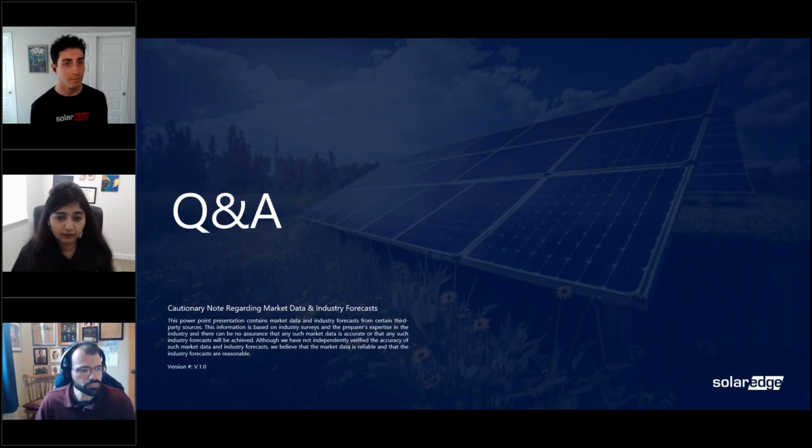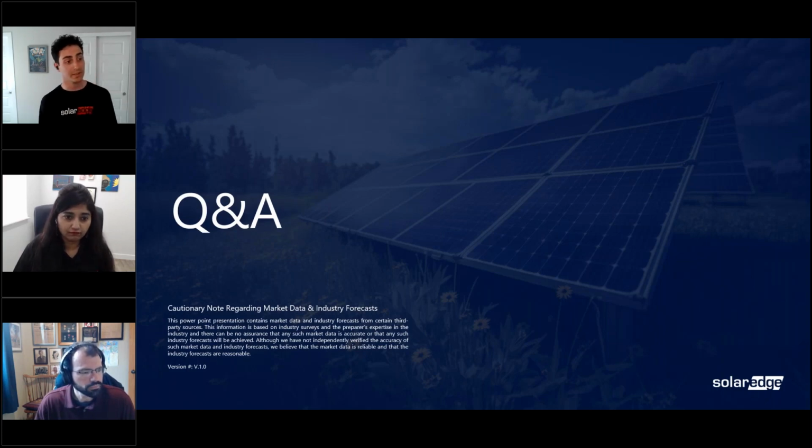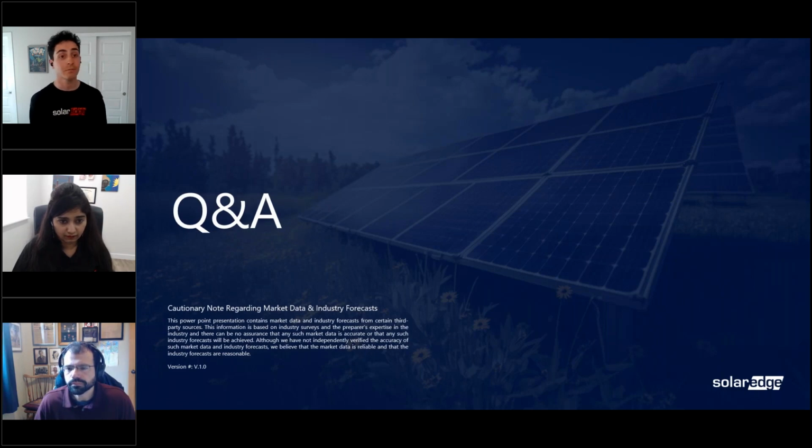Yeah, thanks, Clever. I see a comment from Susan. Susan says Hellermann Titan ties are designed to last 25 years. Yeah, thanks for that comment, Susan. It's a good point. And there are zip ties that are listed with some of these systems that have ratings for longer lifespan. What I would note is that the warranty level on these ties is still usually between 1 and 3 years. So just something to note. And obviously, the concern that we have with zip ties is that you don't know when they break. There's no way to actually know that without going to site and checking in person. Yep. And that's why we mentioned that it's tough to maintain that compliance over the years without checking that they're indeed lasting for that system lifetime.